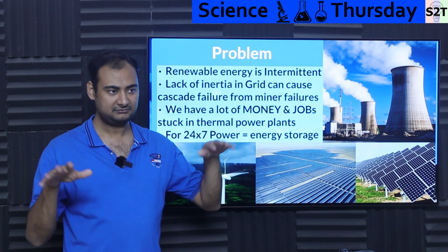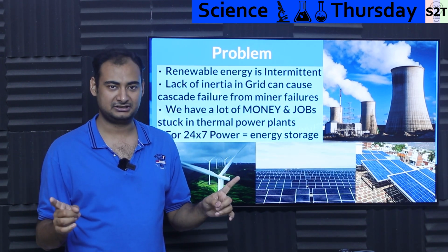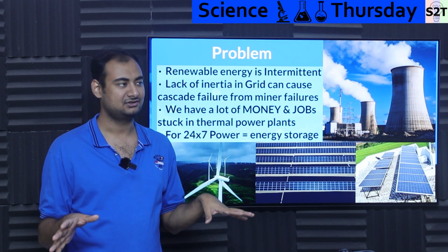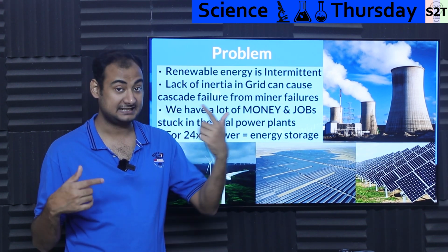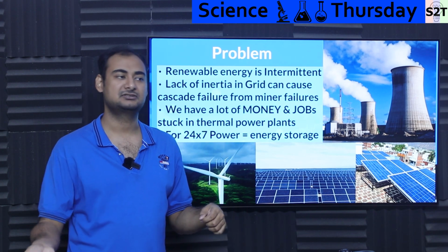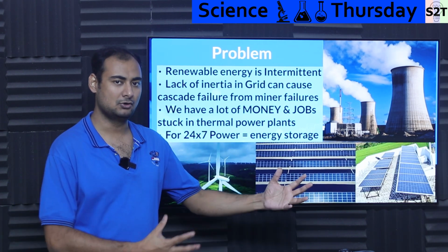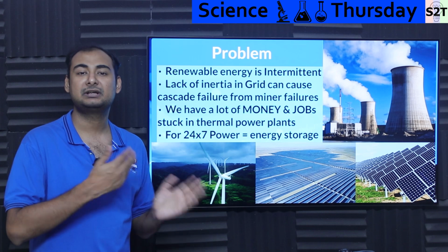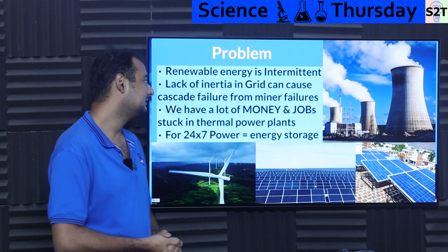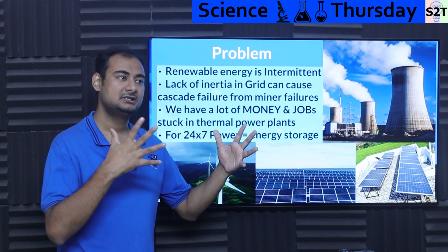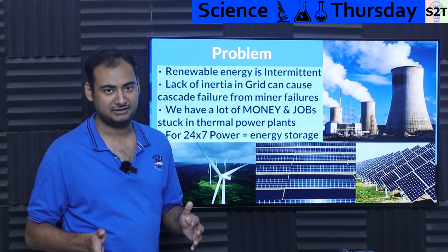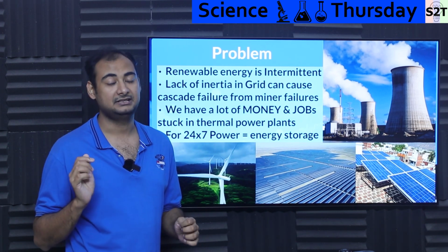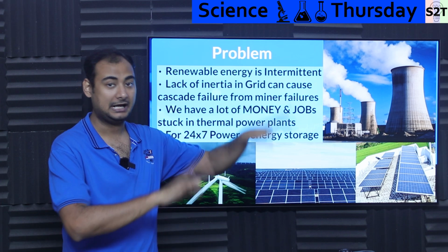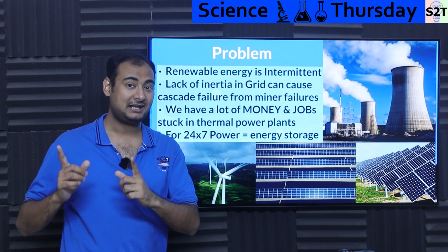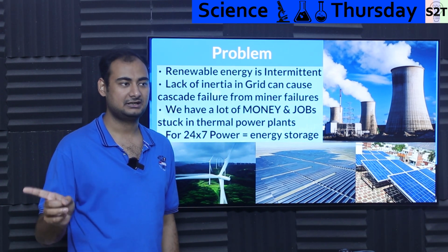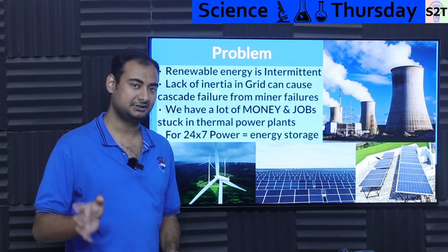Then it will trigger a warning saying there's a big load in demand. Now it's an armed situation. It checks, is the frequency still dropping, as in RPM? If yes, then it opens up the steam valve: more power, more pressure, now you can compensate for that 10 megawatt. That's how our grid successfully manages supply and demand, because demand has no throttle, it can go up and down whenever it wants, but supply has a throttle, so we can cut it.